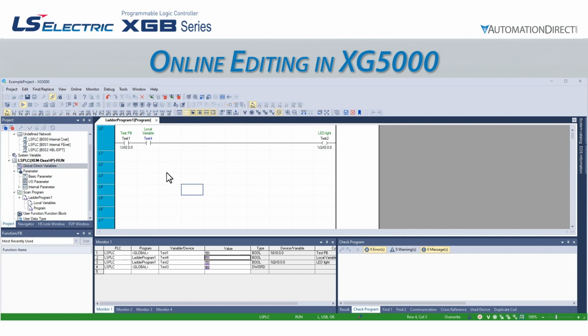Once we have done this, we can make changes to the logic, we can add or delete global or local variables, and we can even edit multiple programs or tasks simultaneously. Note that the logic row numbers change color when we are in online editing mode. Any logic that has been modified but not written to the CPU will be highlighted. This is true for the ladder logic or structured text programming languages. The sequential function chart and instruction list programming languages do not support online editing.